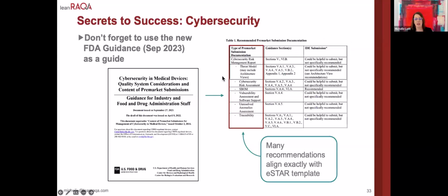So what else is interesting is that I am seeing people, regardless of the classification of their software, the risk level of their product, the likelihood of it having any type of cybersecurity issue, the FDA is requiring all of this documentation, period. Now, maybe your level of detail can vary, but it's a huge undertaking to have a device that has any type of software for any purpose.